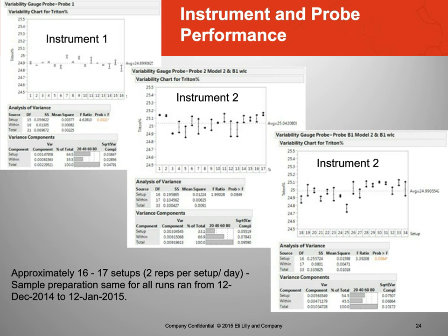We took a look at about a month and a half, about a month's worth of data over several days. We did 2 preps per setup per day, and approximately 16 to 17 samples, and ran them on instrument 1, and probe 1 and 2 on instrument 2, just to compare. On instrument 1, again, this is just one probe. On instrument 2, we have 2 different probes, and we did intensity correction. And we got decent results, and I showed the limits here of 24.5 to 25.5 just to show how well we produced the results. But both probes behave quite nicely between the two instruments.